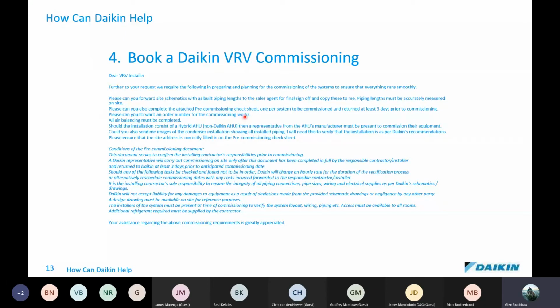We also ask that you complete the pre-commissioning check sheet, which I've just spoken about before this. You forward an order number for the commissioning works, that all air balancing is complete. It's also on the document for pre-commissioning, and I'm going to talk a lot about that later on. Should the installation consist of hybrid units, you need to have a representative from that air handling units manufacturer. They must be present. Okay, and we will sometimes request that you send through images of the condenser installation so that we can just make sure that there's no problems in terms of the piping. Remember, we spoke last week in depth about the piping around the condenser when you're installing it. Okay, and then also please ensure that you give us a site address so that we know where to find you.